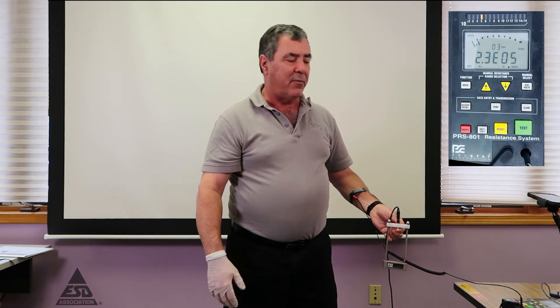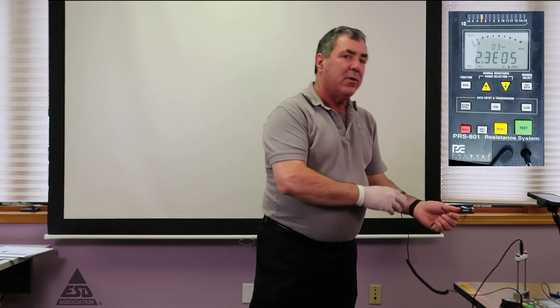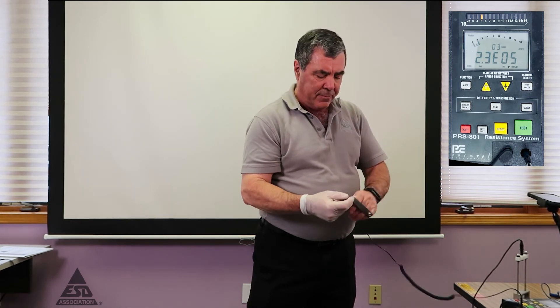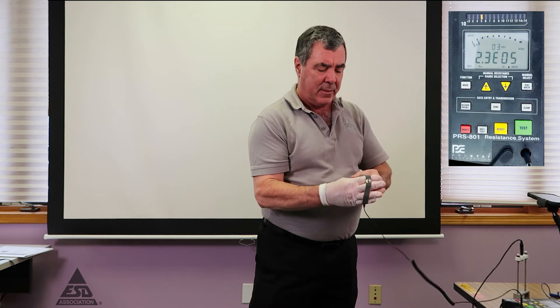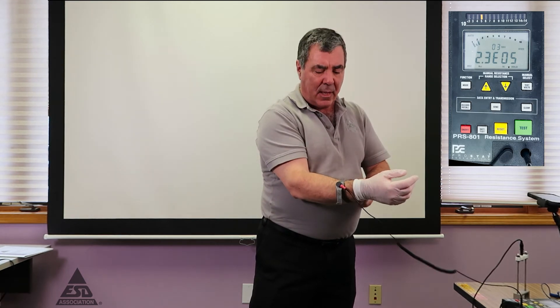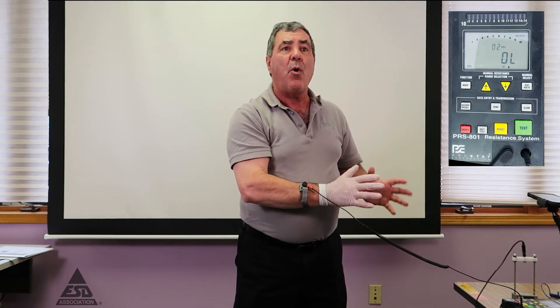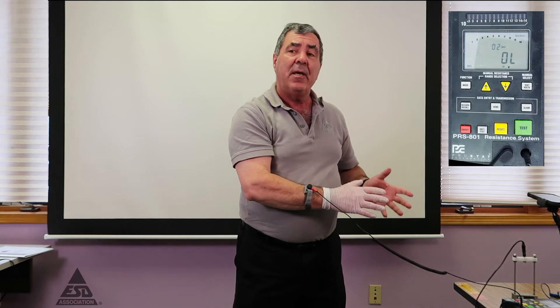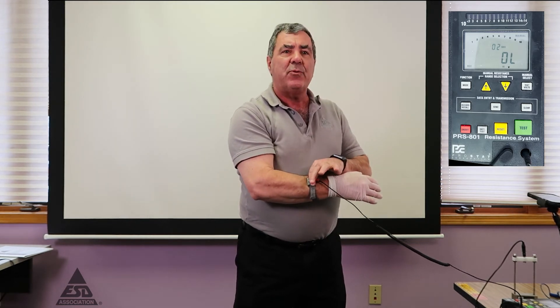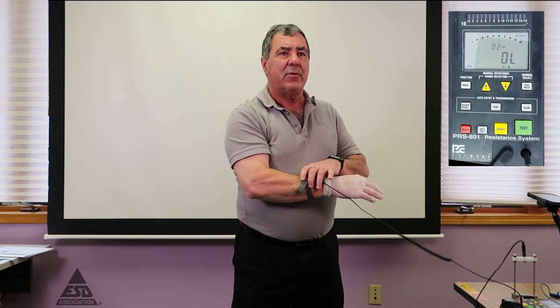The first test, as the standard has it, is to put the wrist strap on the same wrist as the glove. The meter is now set up to do a voltage measurement at only 10 volts. This meter will auto-range unless you change it — I've changed it to manual mode so it's only going to 10 volts. With the wrist strap that has no resistor in it, you only want to test at 10 volts.